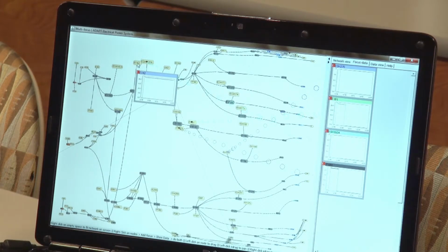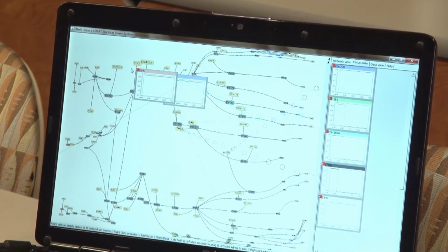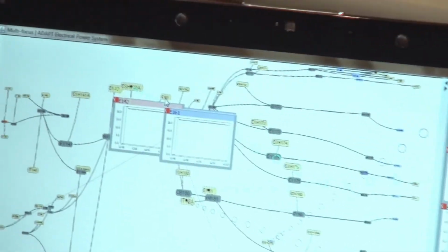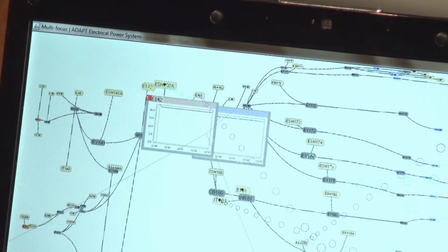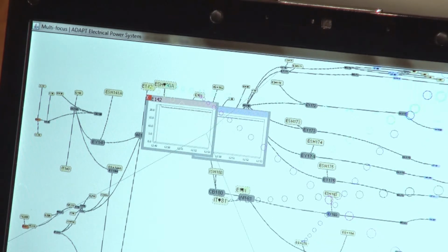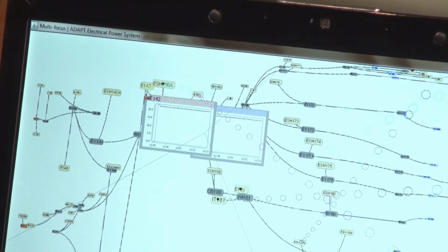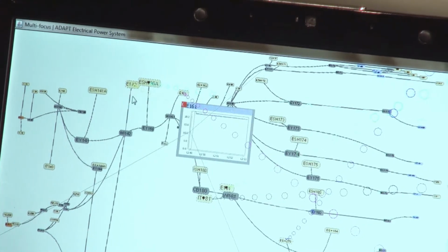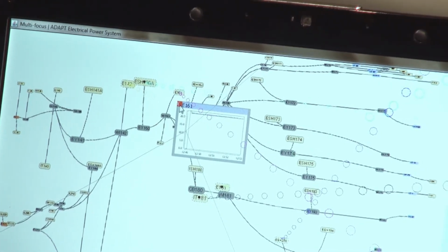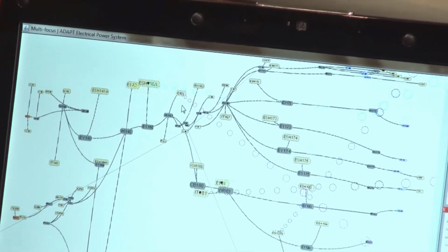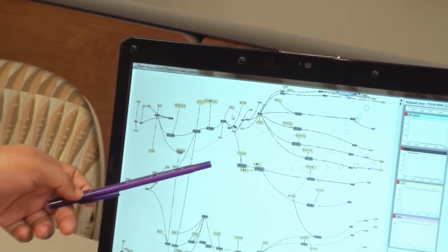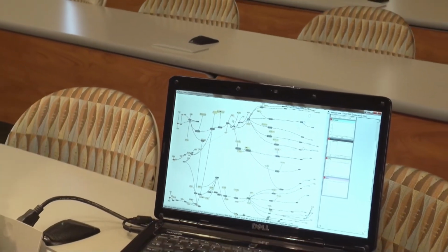Let me open this E142 sensor, which doesn't show a drop in reading. And let me open this one, E161. So even this doesn't show a drop in reading. So this suggests that the sensor here itself is faulty. So we have identified two different faulty components here. One is the circuit breaker, the other one is a sensor.